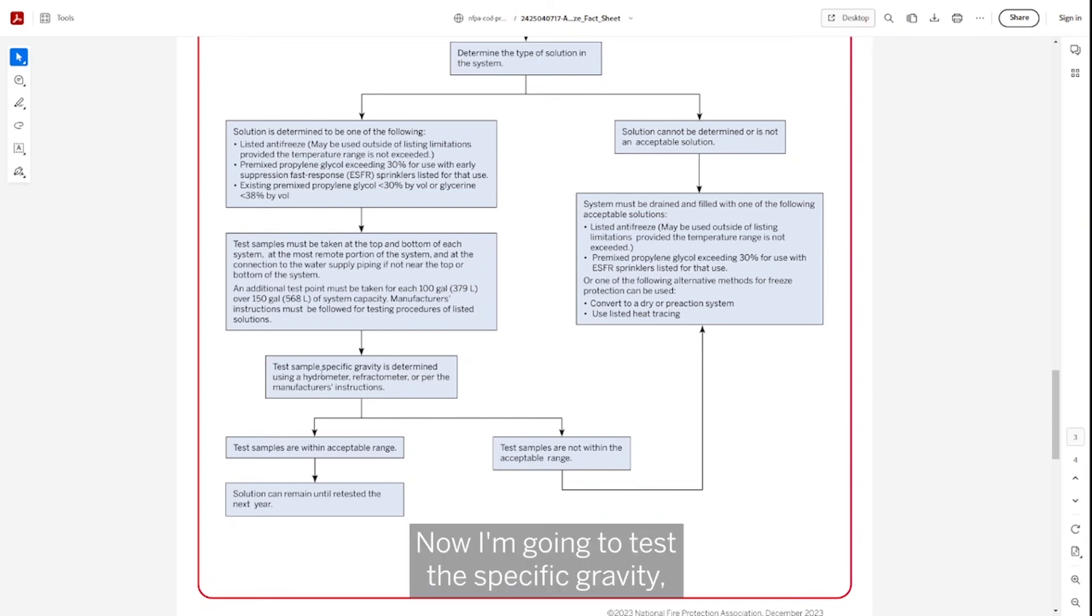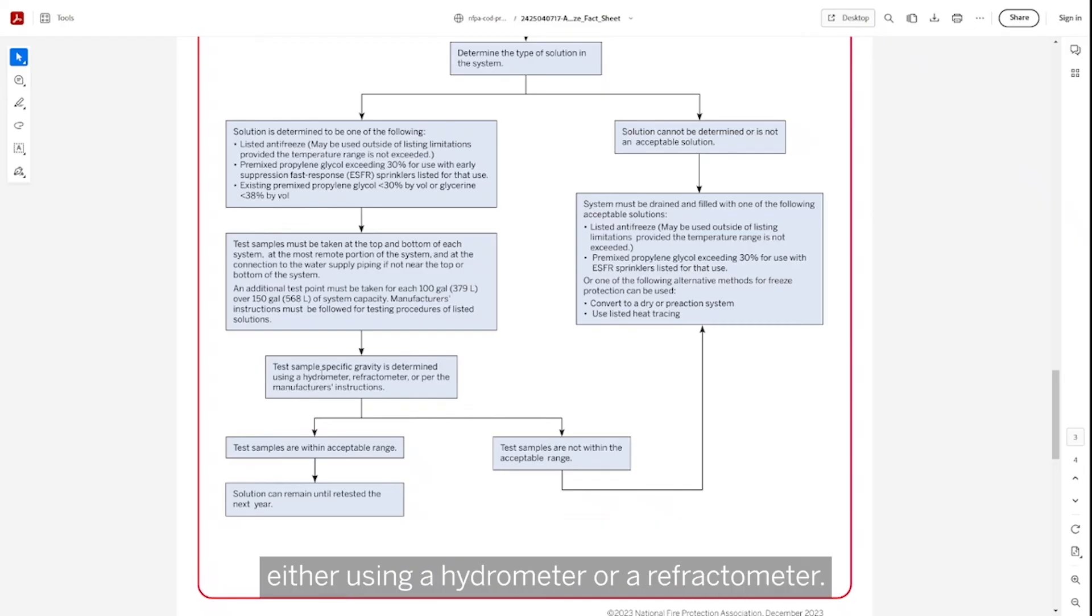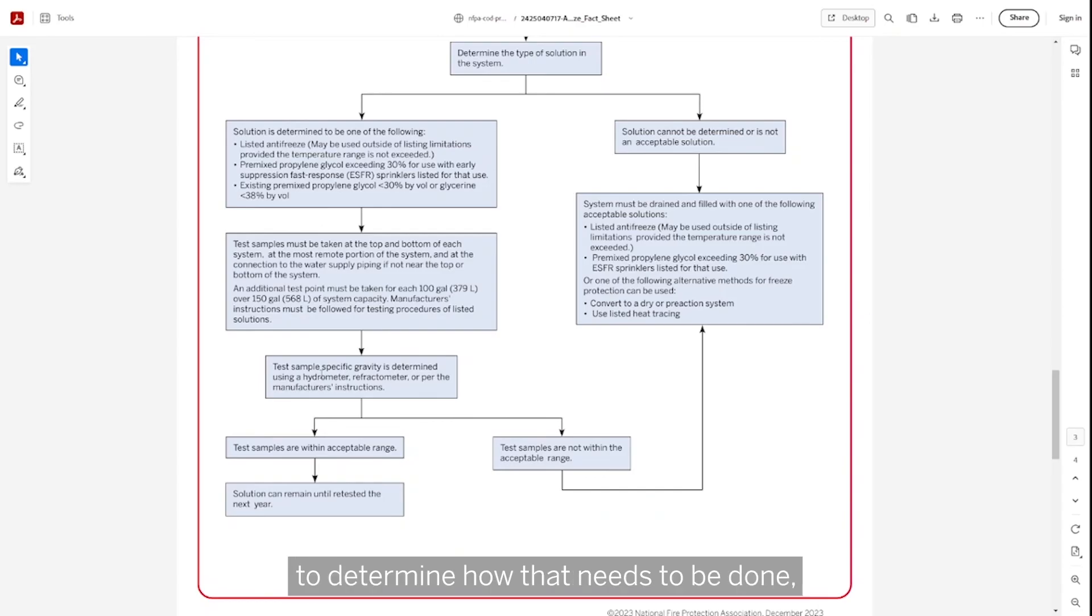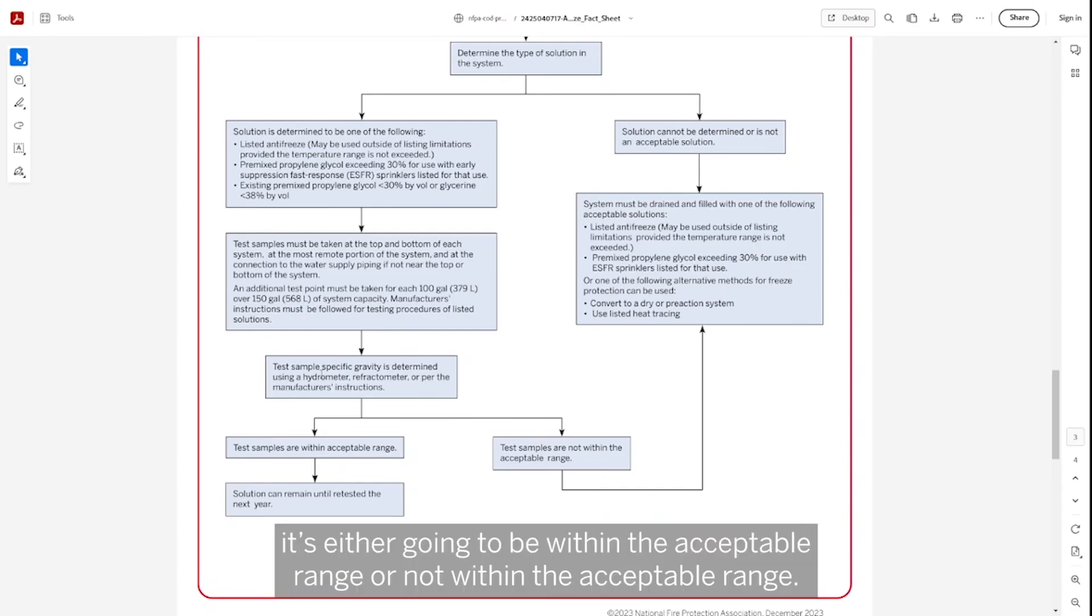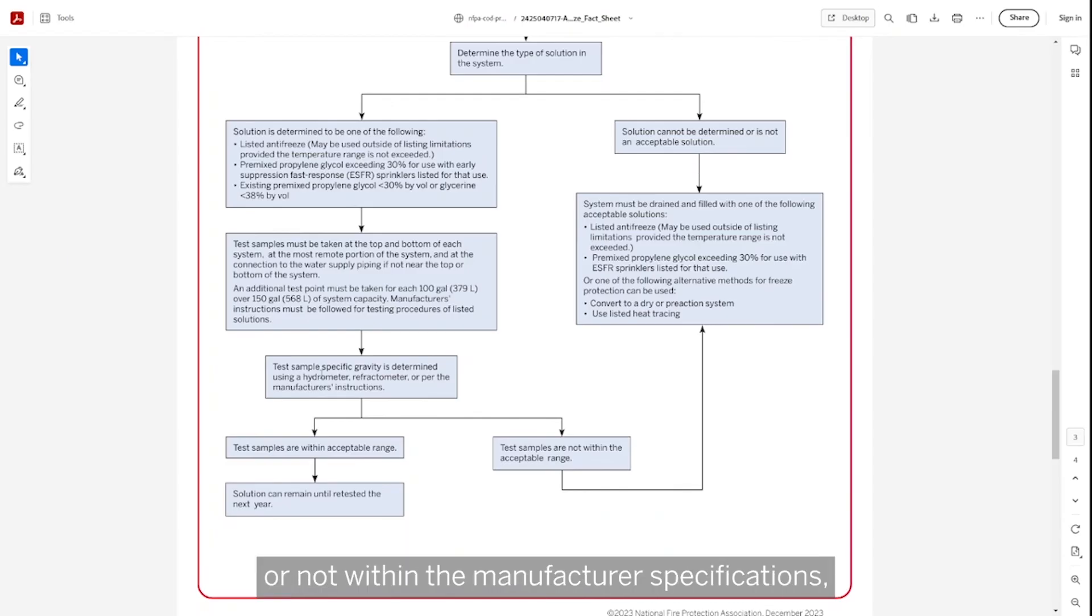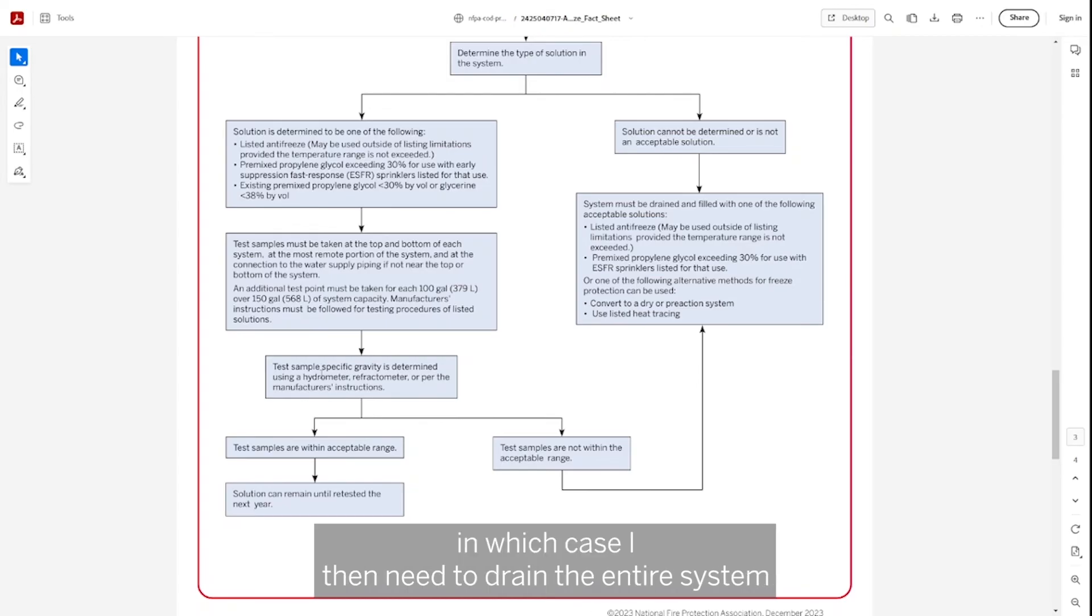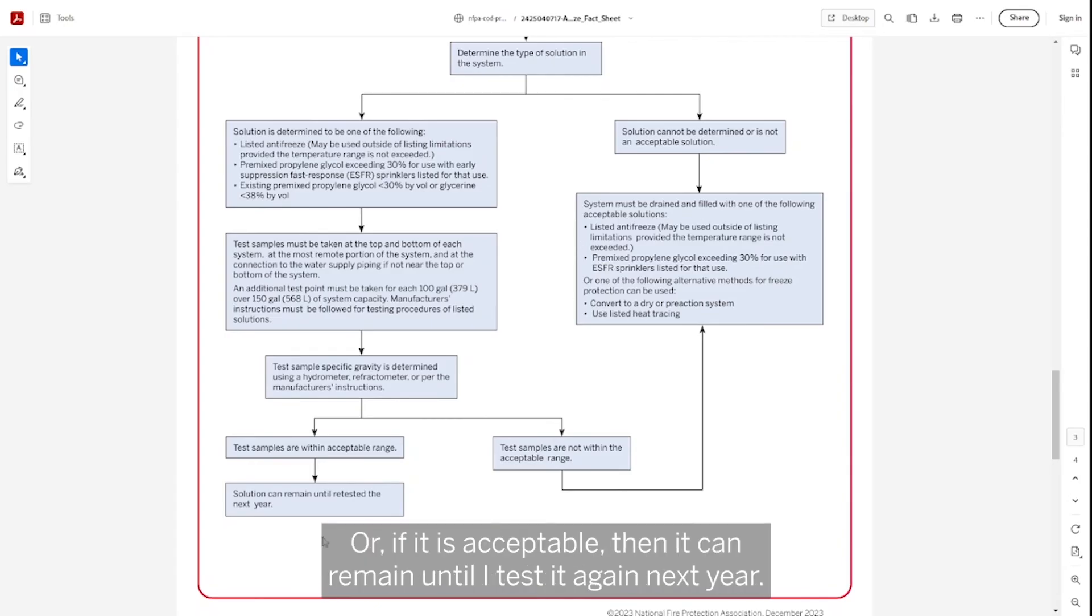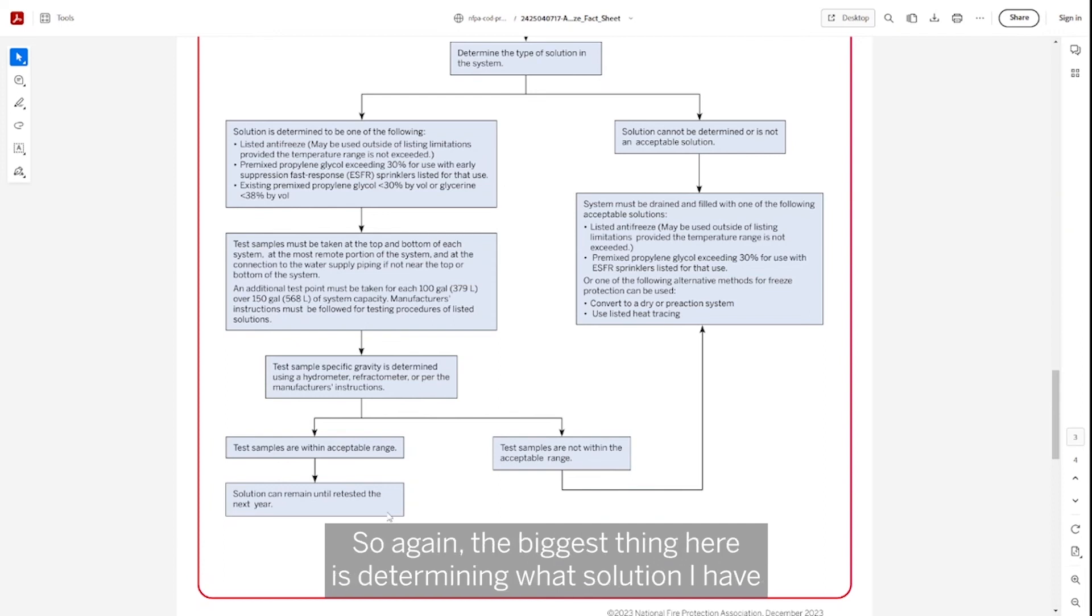Now I'm going to test the specific gravity either using a hydrometer or a refractometer. I need to look in the manufacturer's instructions to determine how that needs to be done. It's either going to be within the acceptable range or not within the acceptable range. If it's not going to provide that freeze protection that I need or not within the manufacturer's specifications, then I need to drain the entire system and replace it with an acceptable solution. Or if it is acceptable, then it can remain until I test it again next year.